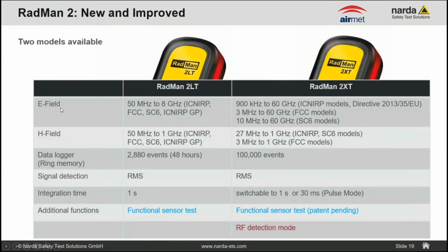As I already indicated, both the electrical field and the magnetic field are being checked. That is in line with the standards. Other differences are not only the frequency range, but also the data logger, which is extended in the extended version. So instead of around 3,000 events, it will log 100,000 events, with signal detection through root mean square.